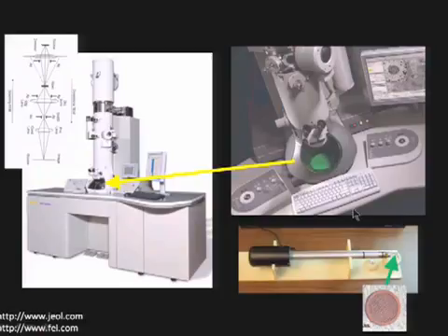And I mean, certainly you can imagine that the sample that you would put in one of these microscopes is super, super small, and this is a sophisticated and sort of challenging imaging technique, but the preparation of the sample is also pretty challenging. You can imagine for an SEM, I mean, you need to prepare your sample and get it on the post and put it in. It has to be conductive and anchored and so on, but to get a good image in TEM, you need to have your sample consisting of the nanostructures you want basically suspended over a hole and thin enough such that the electron beam can get through it.